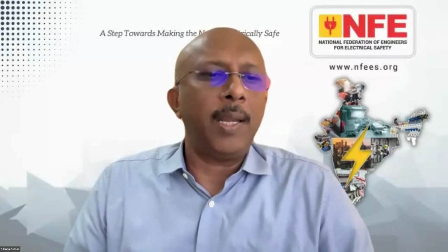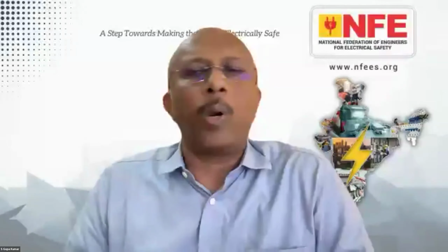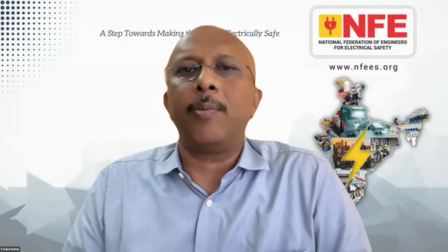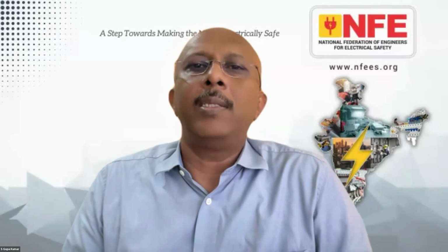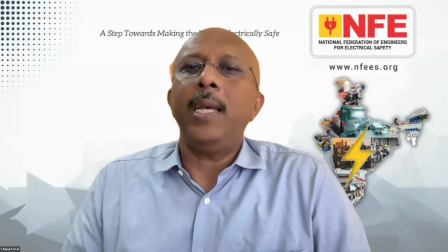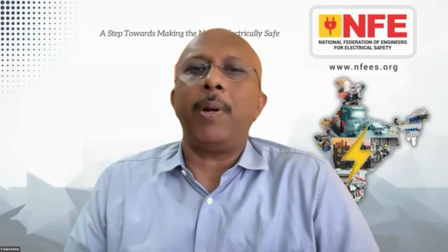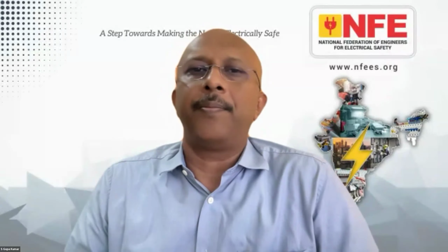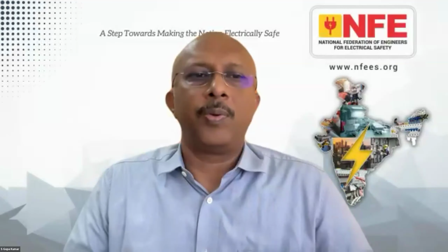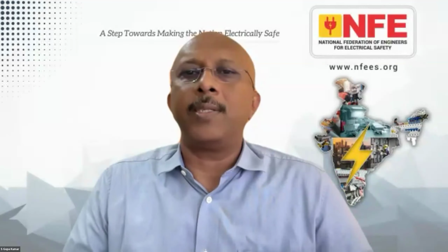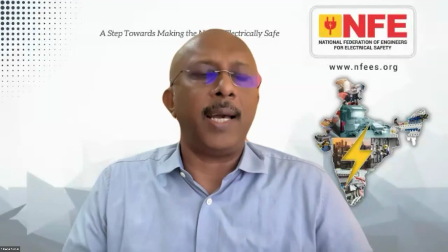Okay, thank you very much. Now we will take one question from the Q&A and then come to the next person. Mr. Imran Maulavi asks: similar to type A RCD, will type AC RCD also get saturated in case of DC pulsating or smooth DC current? Yes. There would be no difference to a type A RCD. It's well dangerous. The AC RCCB would also be saturated if the DC exceeds 6 milliamps. So that means it's extremely dangerous to use a type AC RCD.